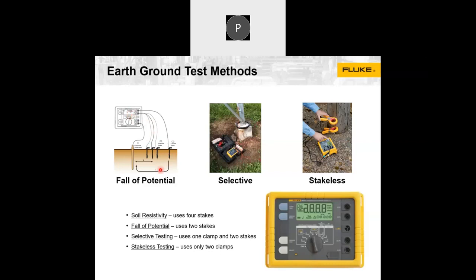Many times when using low-end instruments - I've seen at many customer places they use some 10,000 rupee devices which always give a 'right' reading - this is actually misleading, and they don't know what mistake they are making. When you always get a right reading in earthing, you can be sure the instrument is faulty. I've proven this at least in half a dozen customer locations where I've demonstrated it, and that's why I'm very confidently telling this.